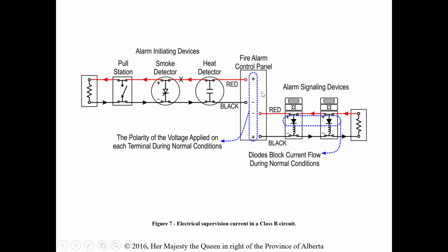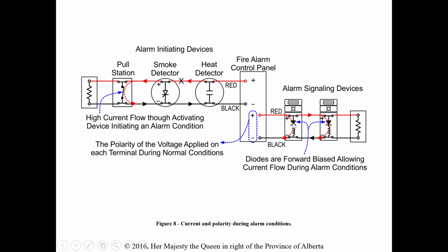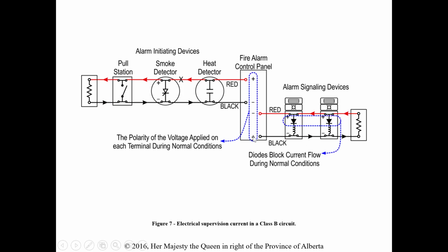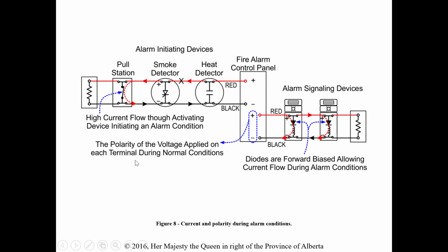So when we get into an alarm situation, we see these signaling devices have diodes in them. Under the normal condition, these diodes are reverse biased, so they don't conduct. Then if we get into an alarm sequence, the panel changes the polarity. What was normally negative here, positive here, is reversed during an alarm condition. Now we have current flow through the diode and then back to the panel. So it's not going to go through the end-of-line resistor, and it's going to activate this device. As soon as these become forward biased, they're going to have current going through them and start signaling. So both of these would start signaling once the polarity is switched at the panel.